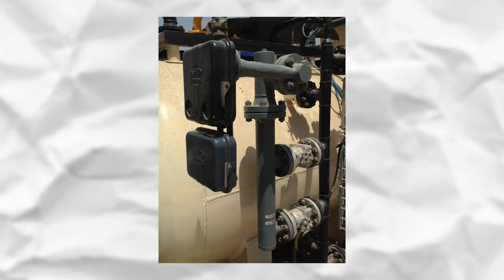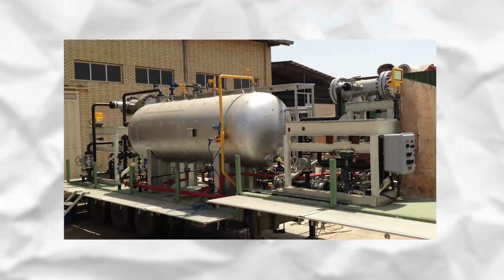Another method of level measurement is the displacer type, which is based on buoyancy force. This type would be really helpful when there is an interface between 2 fluids. Just imagine a separator which is designed to separate oil and water. Since the density of water is greater than oil, water stays lower. To measure the height of water, we are able to install a displacer level meter on the separator, and the time the displacer weight is about to decrease, it is deduced that the height of water becomes higher.